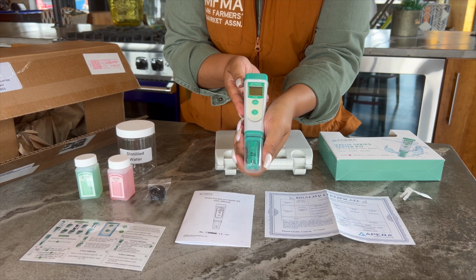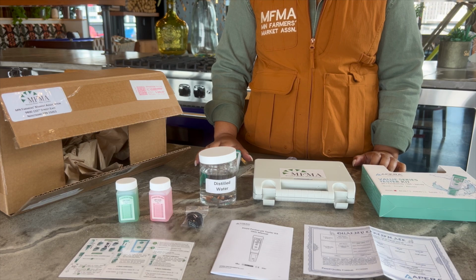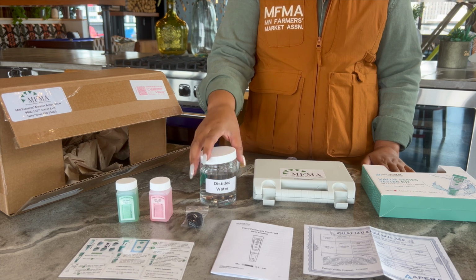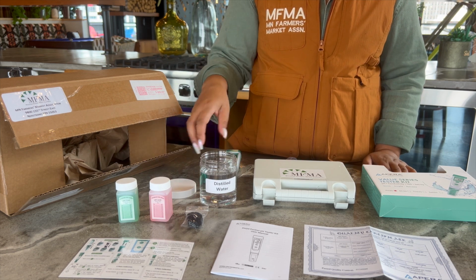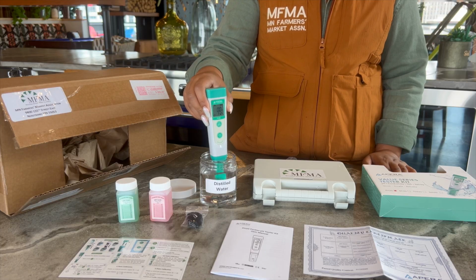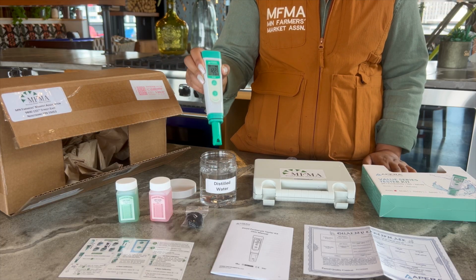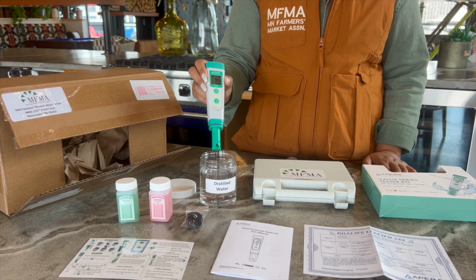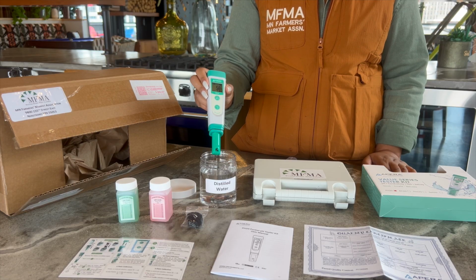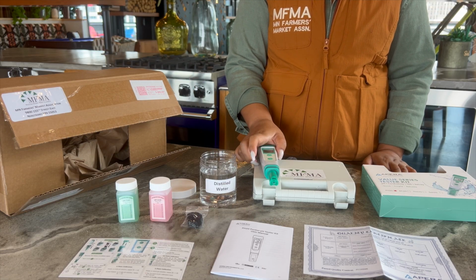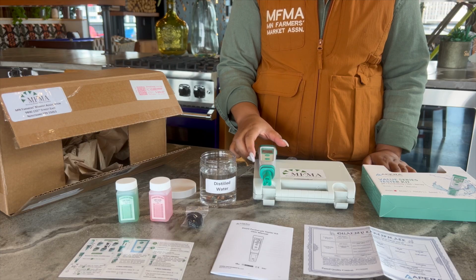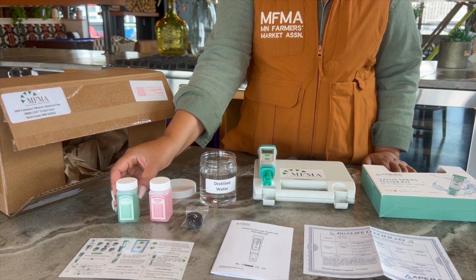Calibrating the Apera pH meter. Step 1. Open the jar of distilled water. Rinse the probe in the water, then shake off excess water. Step 2. With this Apera meter, we start with the 7 pH solution to calibrate. If you have a different brand, follow the directions for your meter.